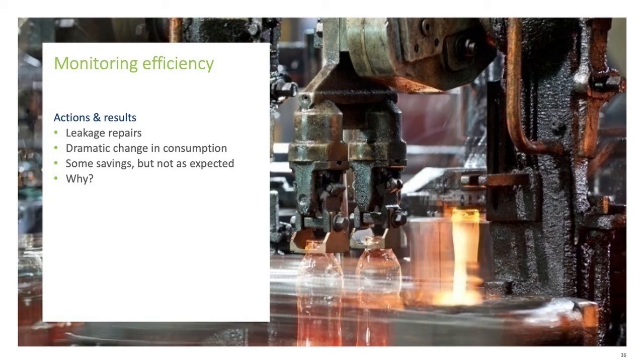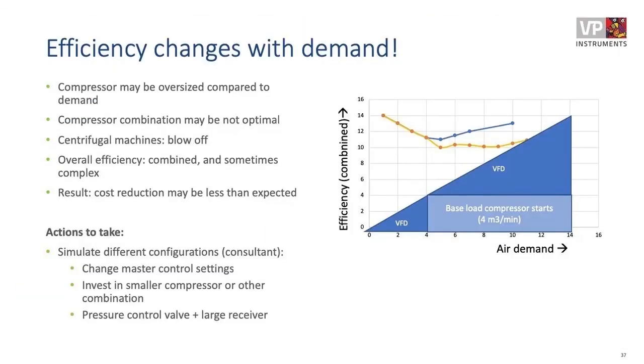What happens in the end, when you have reduced all these leaks, is that the compressor may be oversized compared to the demand, or the combination of compressors might not be optimal. In the case of centrifugal machines, they will probably start to blow off the air which you have saved downstream. But the problem is that predicting this is sometimes pretty hard, because of the overall efficiency of everything combined. When there is a master control already in place, sometimes you don't know exactly the algorithm which is running in this master controller.